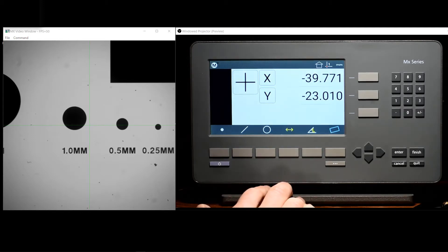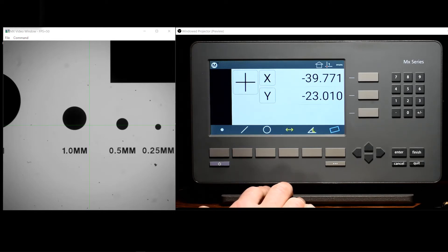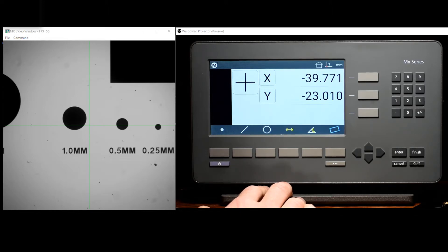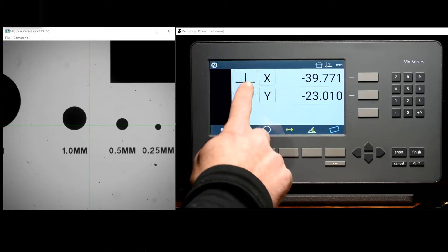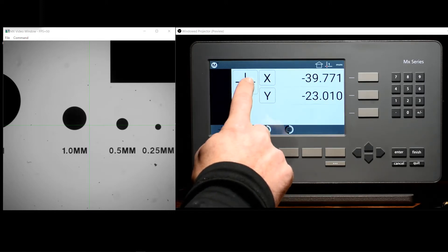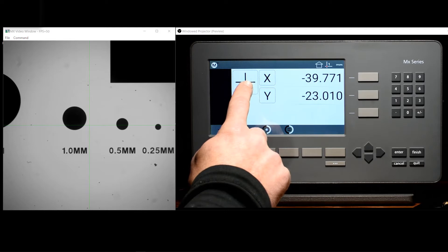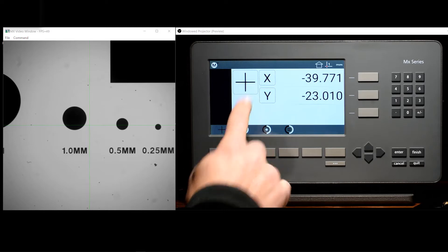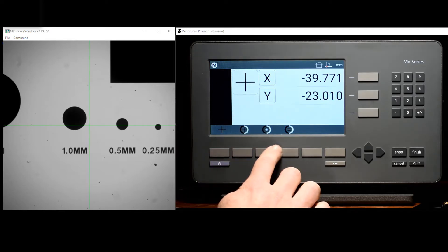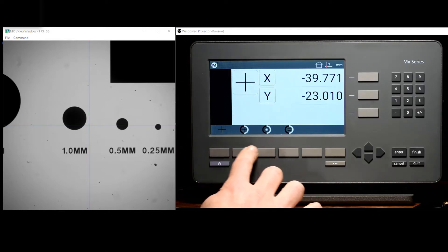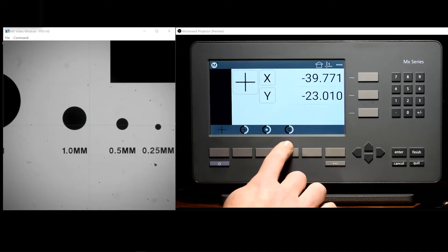For readouts that are mounted to an optical comparator measuring system, the system may be equipped with an optical edge detector. For systems with optical edge detection, the probe menu, accessed by pressing the probe button here, will give you access to the optical edge type probes, as well as the optical edge teach button.